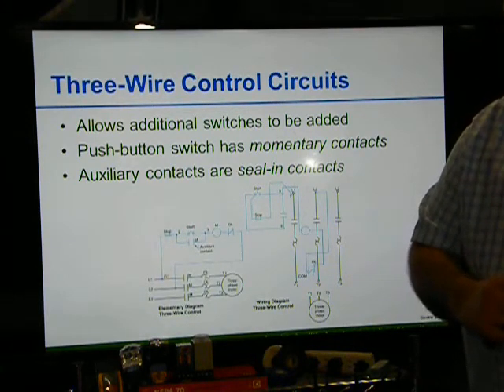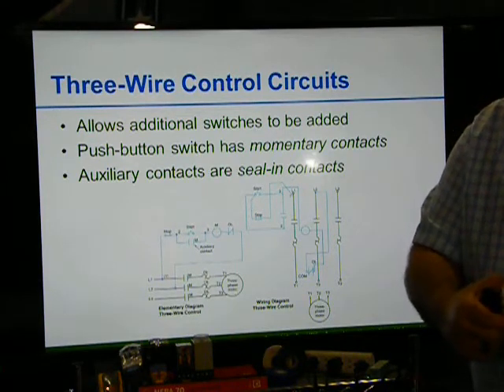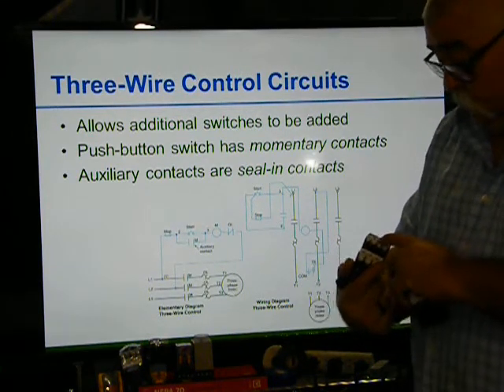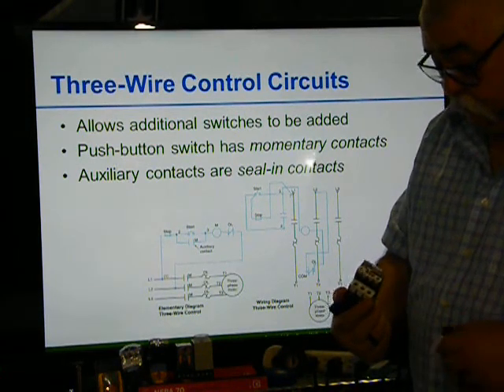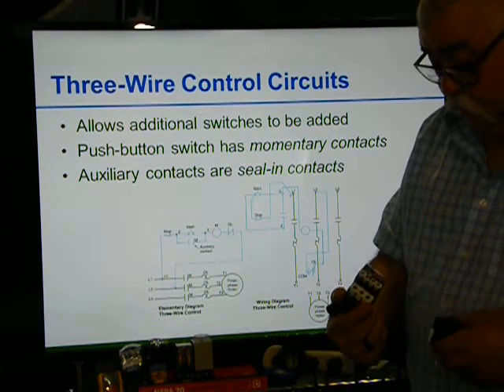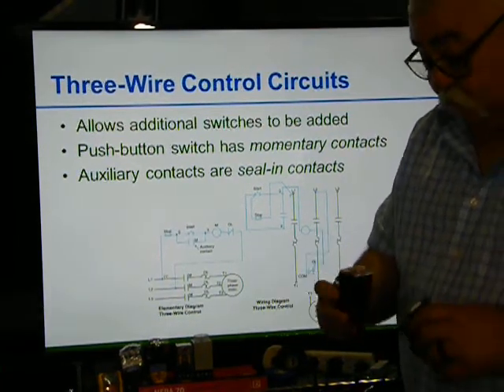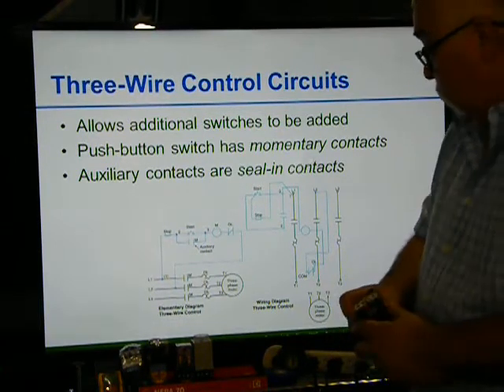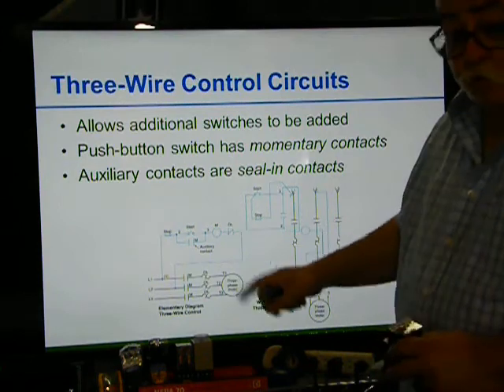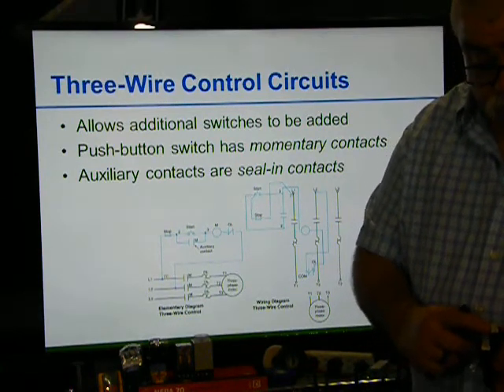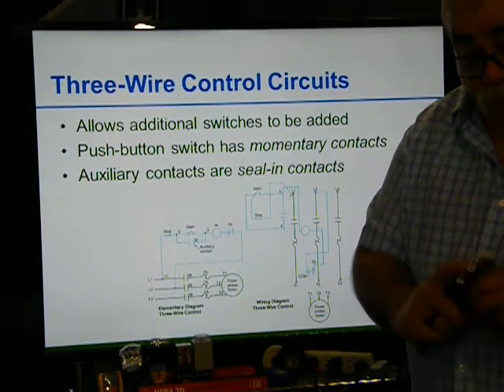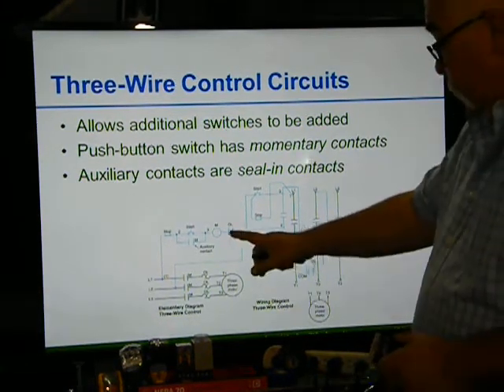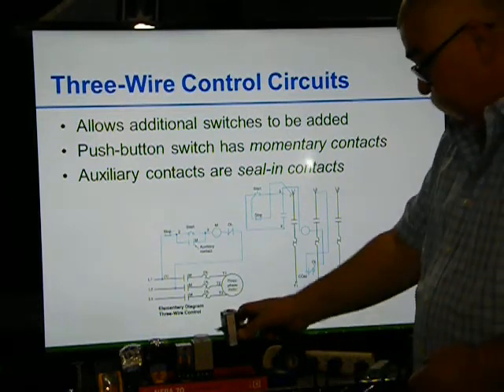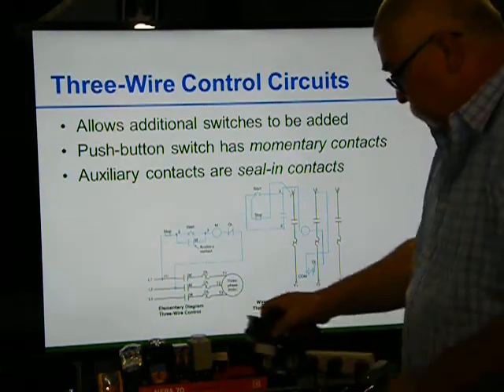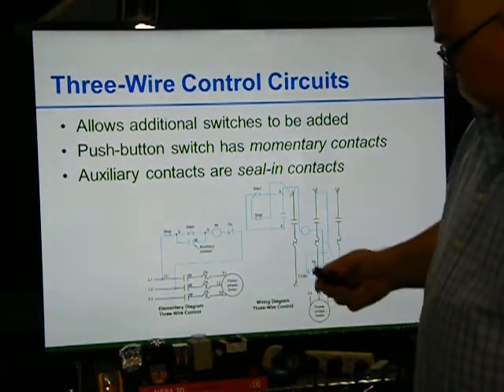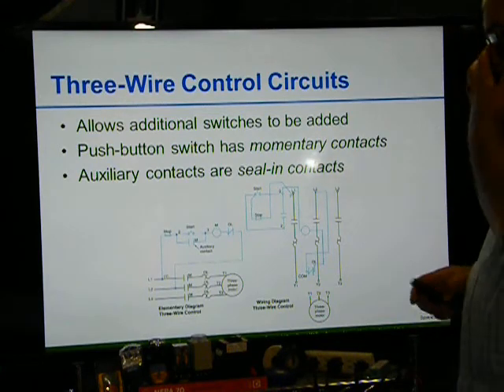Do I want it normally open, or do I want it normally closed? And it gives you both options on this. Normally open, normally closed. Okay, so you set your trips wherever you need them, according to the math, 125% or 115%, depending on what type of motor you got. And again, this one's normally closed, so you would go to the NC. If you want this open, then you go to the NO. Again, diagram between the two, they're both the same diagrams.